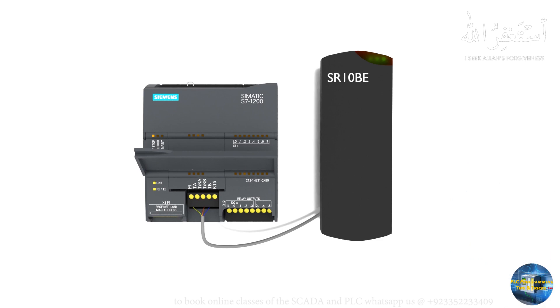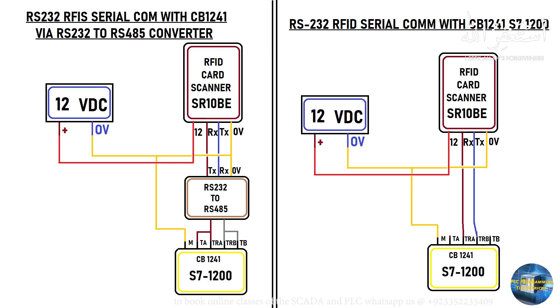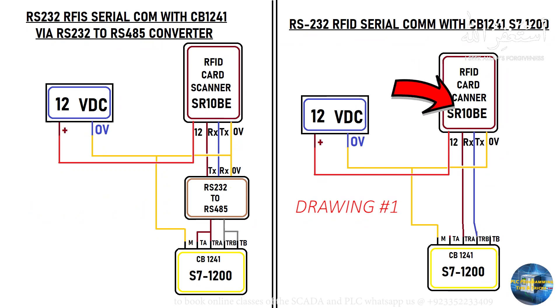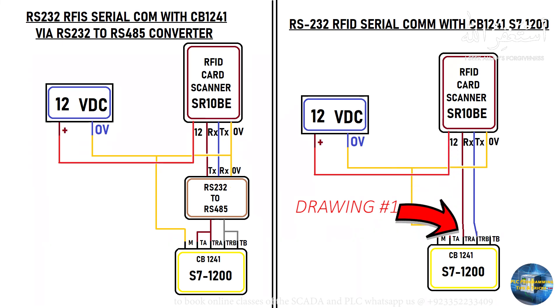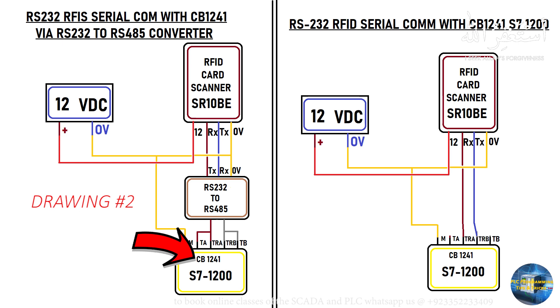Let's first see the wiring diagram for today's project. We are using an RFID scanner with serial data output. We have tested two wiring configurations. In the first diagram, we have connected directly the RS-232 serial RX and TX lines of the RFID module to the RS-485 CB1241 card of the S7-1200 PLC. We have also tested the communication by inserting an RS-232 to RS-485 converter in between the RFID scanner and the CB1241 card, as shown in the second diagram.